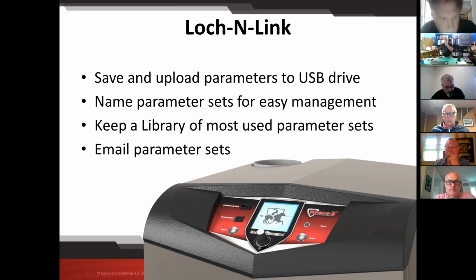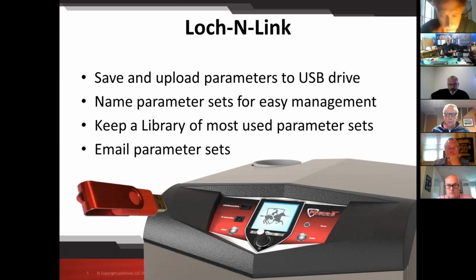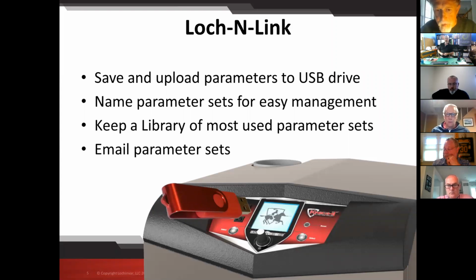The other side is, if you run a plumbing heating company or an HVAC company and you're sending your guys out in the field and you have certain things you like to program, you can go right ahead and pre-program those thumb drives and send them out with your guys, and they can go ahead and just upload that. If you need a pre-programmed thumb drive, you get that through your Lochinvar distributor, or reach out to one of the FIA sales team and they'll get them for you. If you want to set up your own thumb drive, you just need a regular USB thumb drive to go right ahead and do that. Okay, it plugs right in there. And here's the gratuitous animation slide that we have as to how it plugs in. It's a terrible job at docking right there.